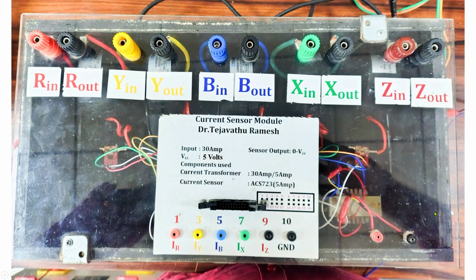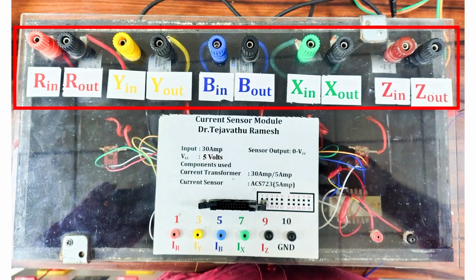Now, let us quickly look at the terminals of this current sensor module. This board is designed for measuring 5-phase currents. At the top side, we have the current input and output terminals for all 5 phases. At the bottom side, one set of output signals is provided for connecting to the ADC pins of the controller. Another set of output points is provided for observing the sensor waveforms directly on the DSO. This is very useful while testing and debugging the module.